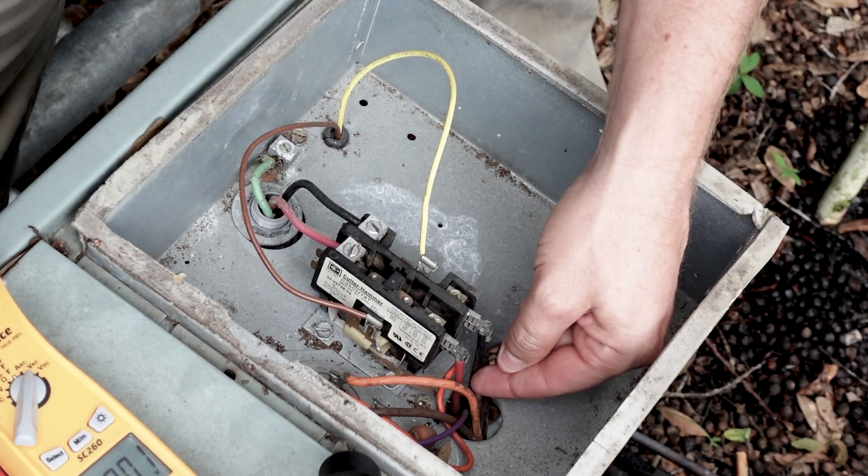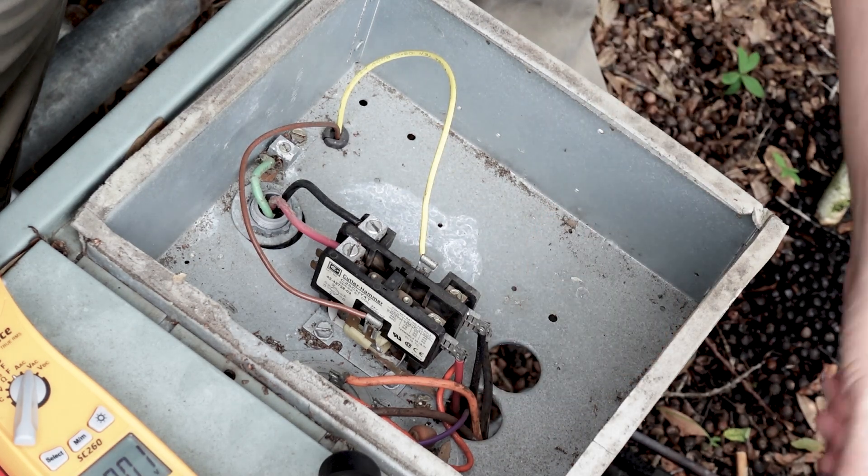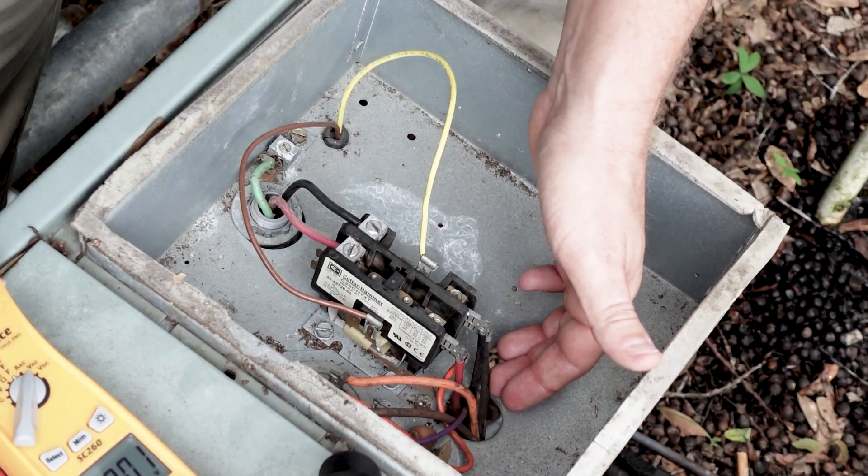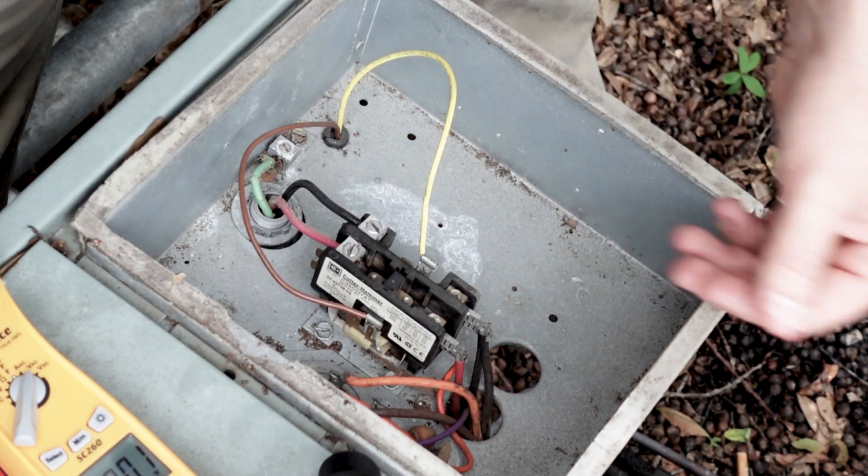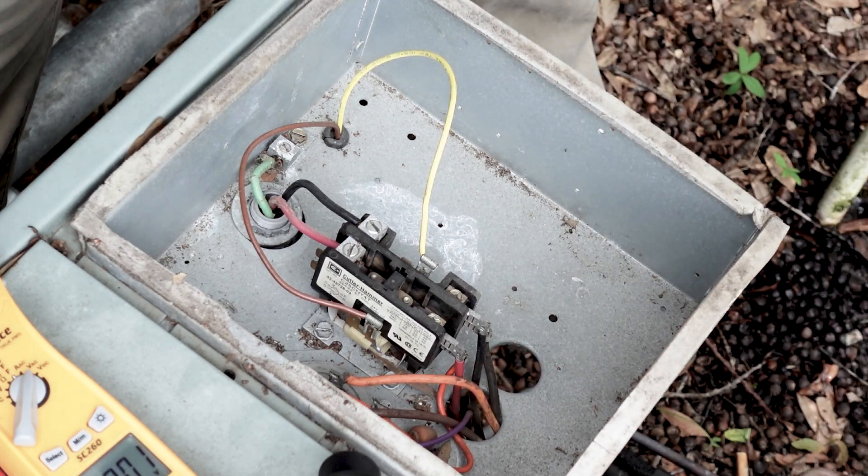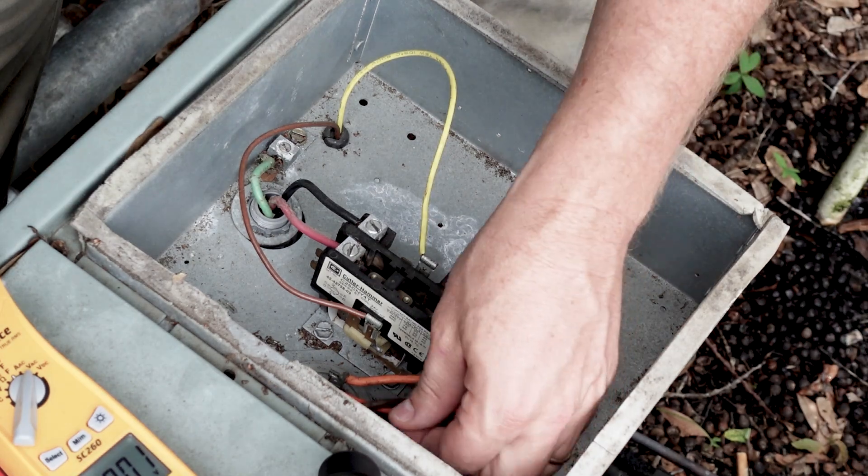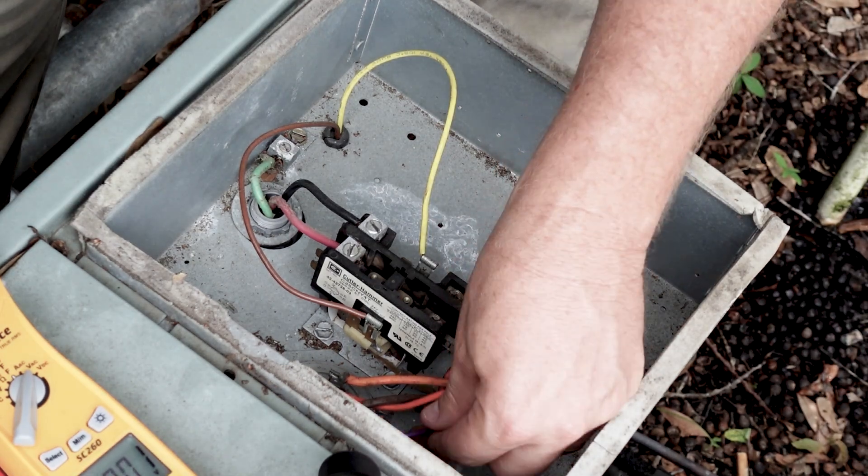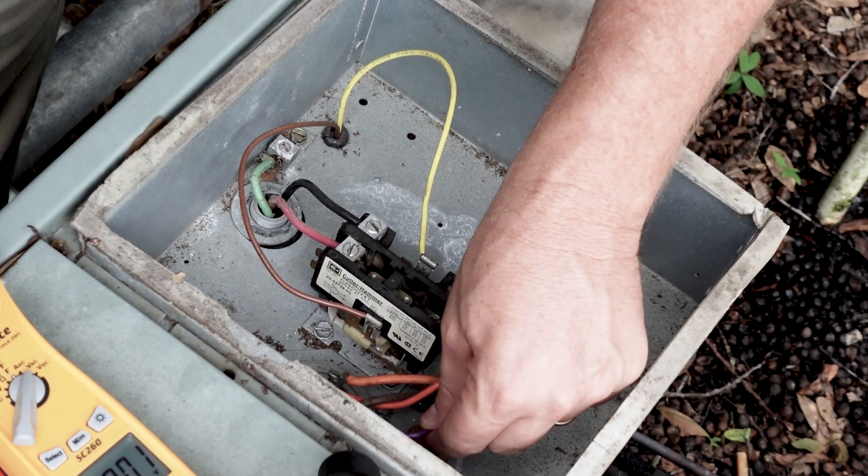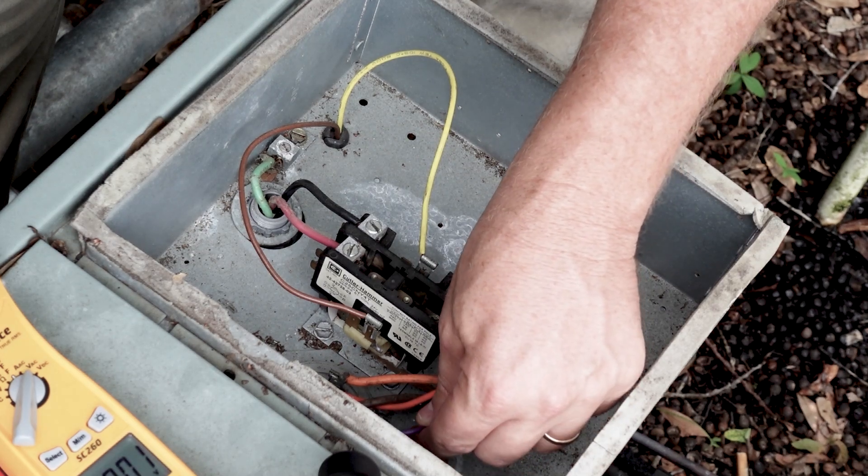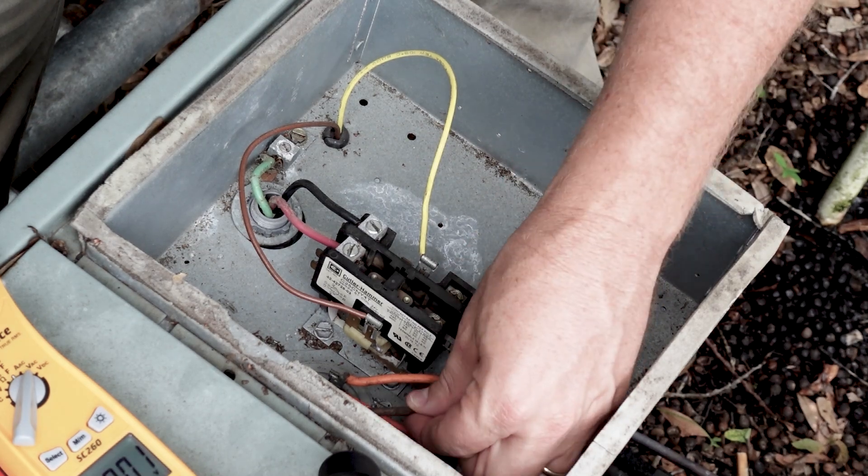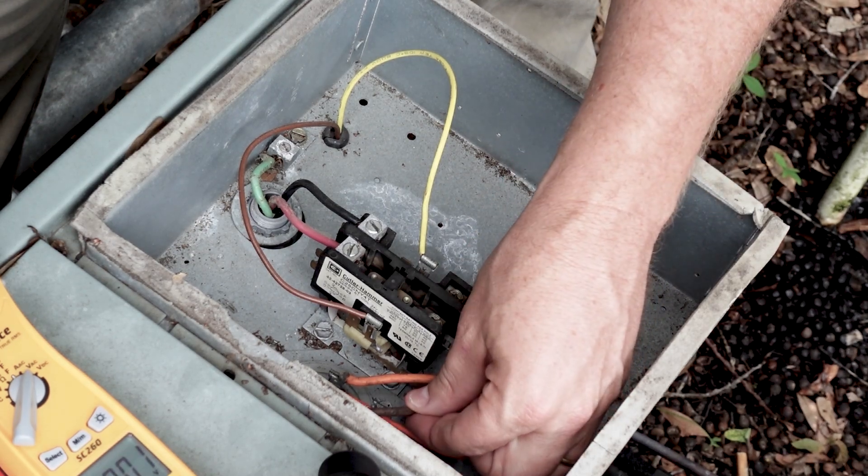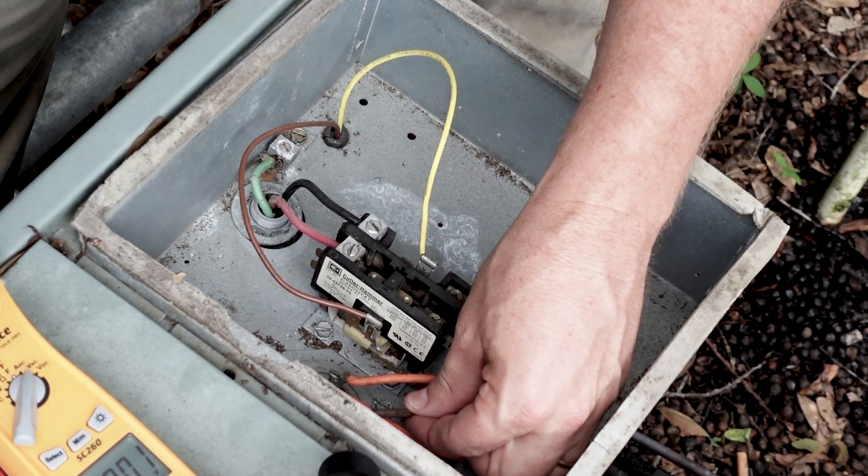One of the blacks, the larger one is going to go to our compressor, which is our compressor common. The other one is going to go to our fan, which is our fan common. We have this purple wire here, which goes to our compressor start winding. And then we have this brown wire, which goes to our fan start winding.